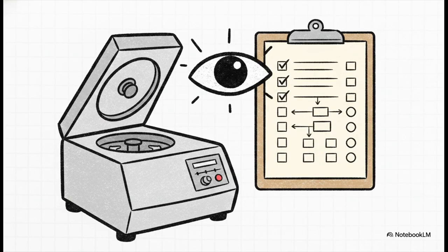So to see how this all builds into a totally airtight system, we look at documentation. The only way to really enforce this level of consistency is to prepare proper standard operating procedures, SOPs, for every single instrument and testing method. But just writing them down isn't enough. They have to be visually displayed right next to the instruments. That way, all staff, no matter their experience level, are constantly aware of the exact right way to operate.